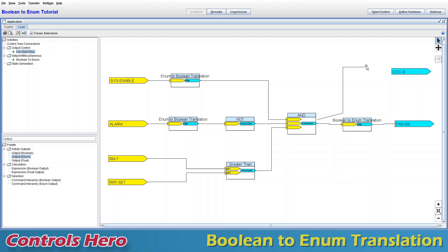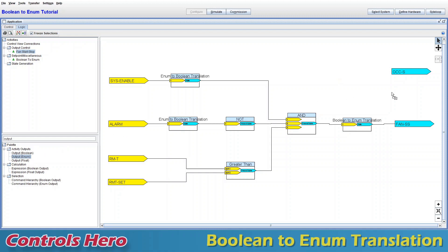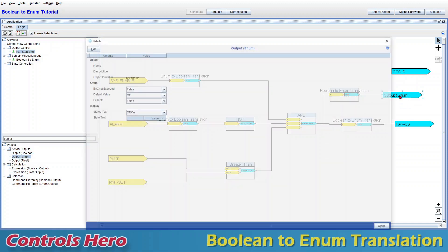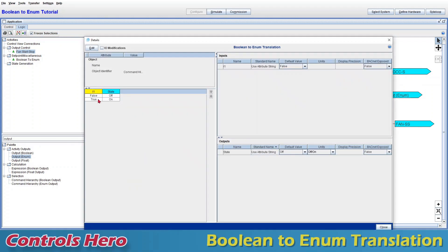Let's try to make the connection straight from my AND block to my occupancy status — and the connection is not allowed. Data types do not match: my source is boolean and my destination is a multi-state. To understand why, I'll create a default enum output and try connecting it — and in that case we can auto-generate the translation because the default enum has two states: off and on. Boolean has true and false, so it can match to those two states. But my occupancy status uses occupancy effective units, which is a multiple-state enumerator.